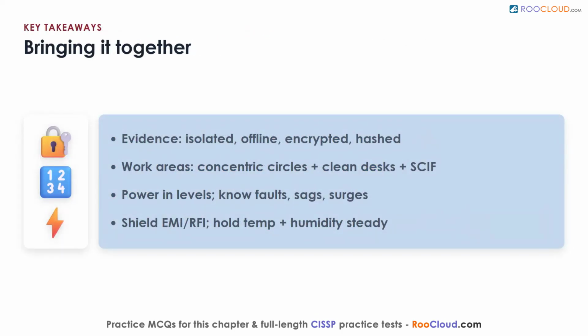So let's bring it together. Store evidence on an isolated, offline, encrypted system with tracked activity and per dataset hashes, so it stays defensible. Design work areas as concentric circles, using solid walls, clean desks, classification, and escorts, with a sensitive compartmented information facility at the top. Protect power in levels, from surge protectors up through conditioners, uninterruptible supplies, and generators, and learn the vocabulary of faults, sags, and surges. Shield against electromagnetic and radio noise, and hold temperature and humidity steady to stop chip creep, corrosion, and static. Nail these utilities, and your equipment runs clean, cool, and continuously.